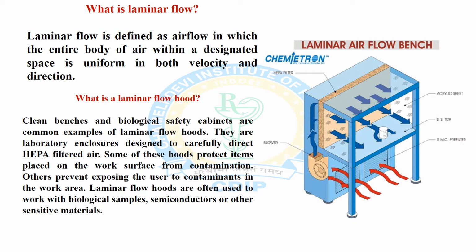They are laboratory enclosures designed to carefully direct HEPA filtered air. Some of the hoods protect items placed on the workspace or surface from contamination. Others prevent exposing the user to contaminants in the work area. Laminar flow hoods are often used to work with biological samples, semiconductors or other sensitive materials. So here is a diagram of a laminar airflow bench.